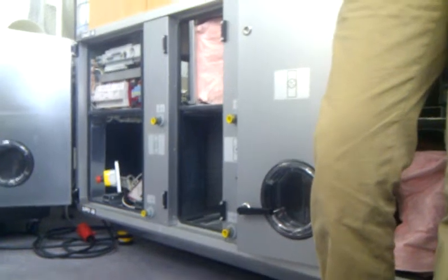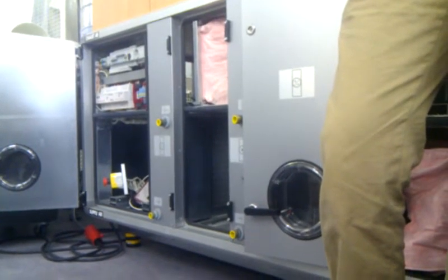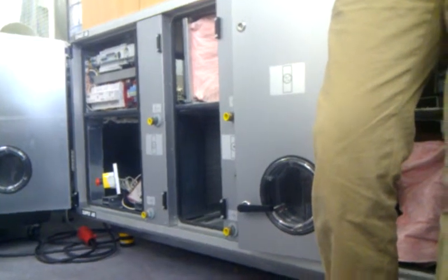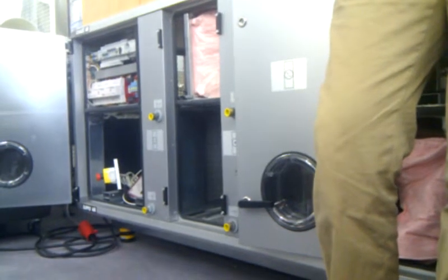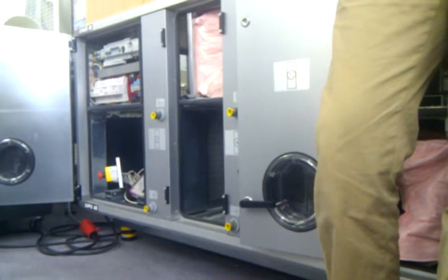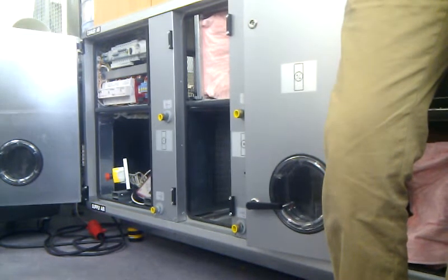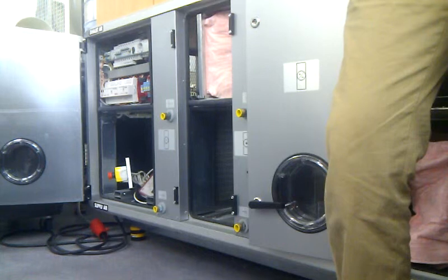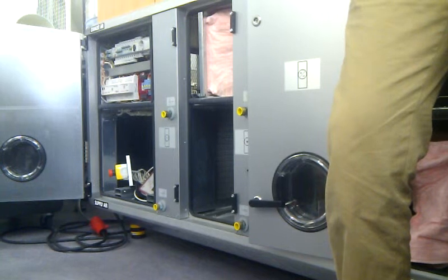And normally, these analog signals are either currents or voltages. So normally you'd have something like 4 to 20 milliamps, or 0 to 10 volts. For most of this stuff, it's 0 to 10 volts, or 2 to 10 volts for some of them, but 0 to 10 mostly. And if you had a 0 to 10 volt signal and you wanted to turn it into a 4 to 20 milliamp signal, what would you do?